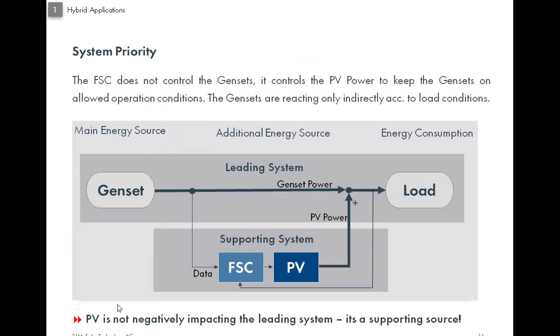One very important thing to note here is that people are often concerned that the Fuel Save Controller will interrupt the gensets, or it may harm the gensets. We should realize that this is a total misconception. The Fuel Save Controller does not control the genset at all. It is only controlling the PV power, keeping in mind the load requirement at any given point of time. And I'll explain in further detail why I am saying this.